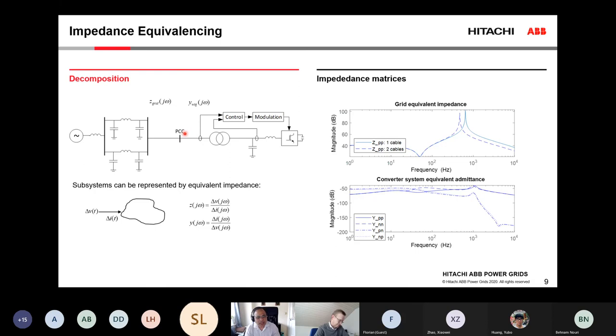If you have a strong grid and then put a current source at the point of common coupling with certain frequencies, say j omega, then the majority of the current actually gets absorbed by the grid side. So it does not excite the frequency domain behavior of the converters because it doesn't get enough signal. So we did something different: rather than having a current source, we put in a voltage with an appropriate frequency. But then we realized that, because you're talking about MMC converters, unless you represent all their control and the delays, the impedance that you are getting is not the actual impedance. What is your thought about it?